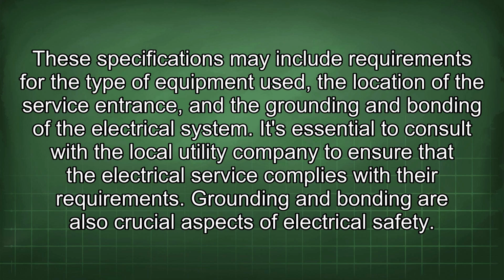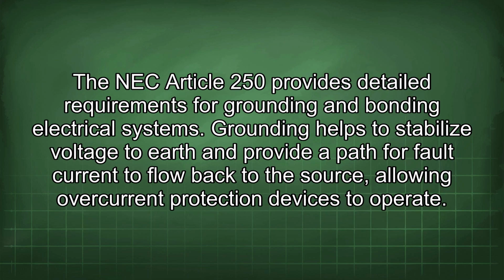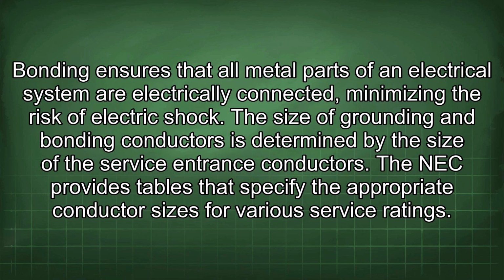Grounding and bonding are also crucial aspects of electrical safety. The NEC Article 250 provides detailed requirements for grounding and bonding electrical systems. Grounding helps to stabilize voltage to earth and provide a path for fault current to flow back to the source, allowing overcurrent protection devices to operate. Bonding ensures that all metal parts of an electrical system are electrically connected, minimizing the risk of electric shock.